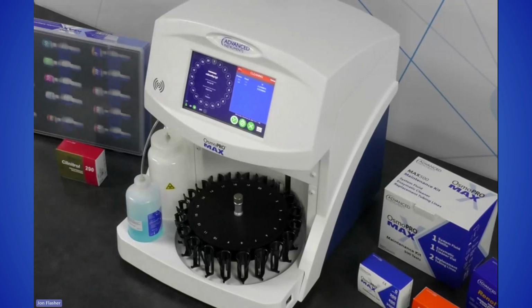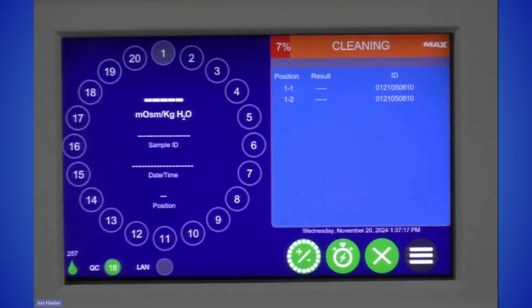So now that we've run a sample, I'm going to go ahead and show you what it looks like on the screen here. Okay, so as you can see, we pre-programmed the instrument to run duplicate tests for a sample that we put in a single position. So over here on the right hand, you'll see 1-1 and 1-2. That's because both tests are going to be run on position 1. So that's what's on the left side of the dash. And then on the right side of that dash is 1 and 2 for each of the tests it's going to run. The results are going to populate under the results section. And your sample ID is over there on the right. So that's where your accession number would live.